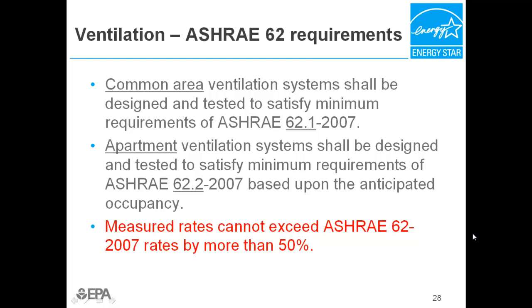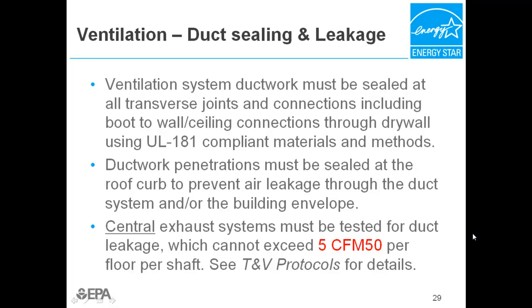Overventilation consumes extra energy, which can be captured through energy modeling in the performance path, but not in the prescriptive path. In the prescriptive path, all ventilation ductwork must still be properly sealed, and central exhaust systems are still tested for leakage. However, the amount of leakage allowed in the prescriptive path is cut in half compared to the performance path.